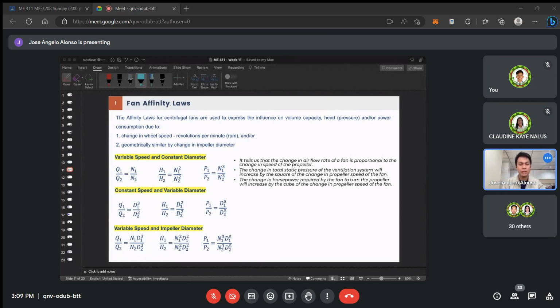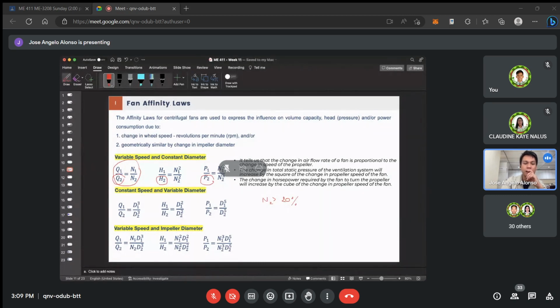So numerically, check natin kung ilan yung mababago. Magkakaroon ng 72.8% increase pala ng power requirement o power input kapag binago natin yung speed ng fan by 20%. So dito class, initially, directly proportional lang. Kung ang N2 natin ay increased by 20%, ang ating Q2 o fan capacity ay magiging increase din by 20%. Ang ating total head ay magiging increase ng around 44%, at ang power required o power input ay magiging increase ng around 72.8%. Yun yung variation niya, yun yung magiging effect o performance ngayon ng ating fan kapag binago natin yung speed pero maintain natin yung diameter.